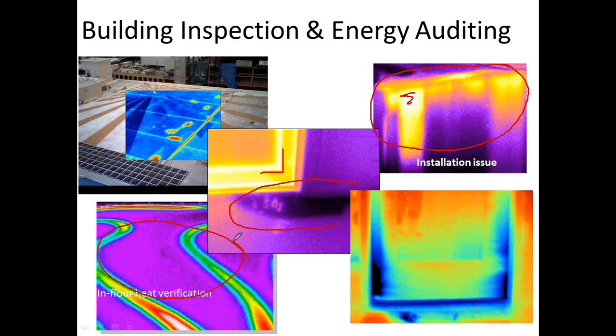The left-hand image is a mud jacking case where they were going to drill a hole, and of course Murphy would be there and they would drill a hole right through one of the tubes. Well, we just had them turn the system on. We marked out the floor, and now the instructions are, you can drill 1,000 holes, just stay 2 inches away from one of the lines to effectively facilitate the mud jacking without damaging the heat coils. And the lower right-hand image, here is the rough opening for the window, and you can see that that has good integrity. It looks like the insulation was done well. What we're seeing is cold air blowing in. Actually the glazing around the glass had degraded, and this would be that cold, drafty feel that you would feel in a room.